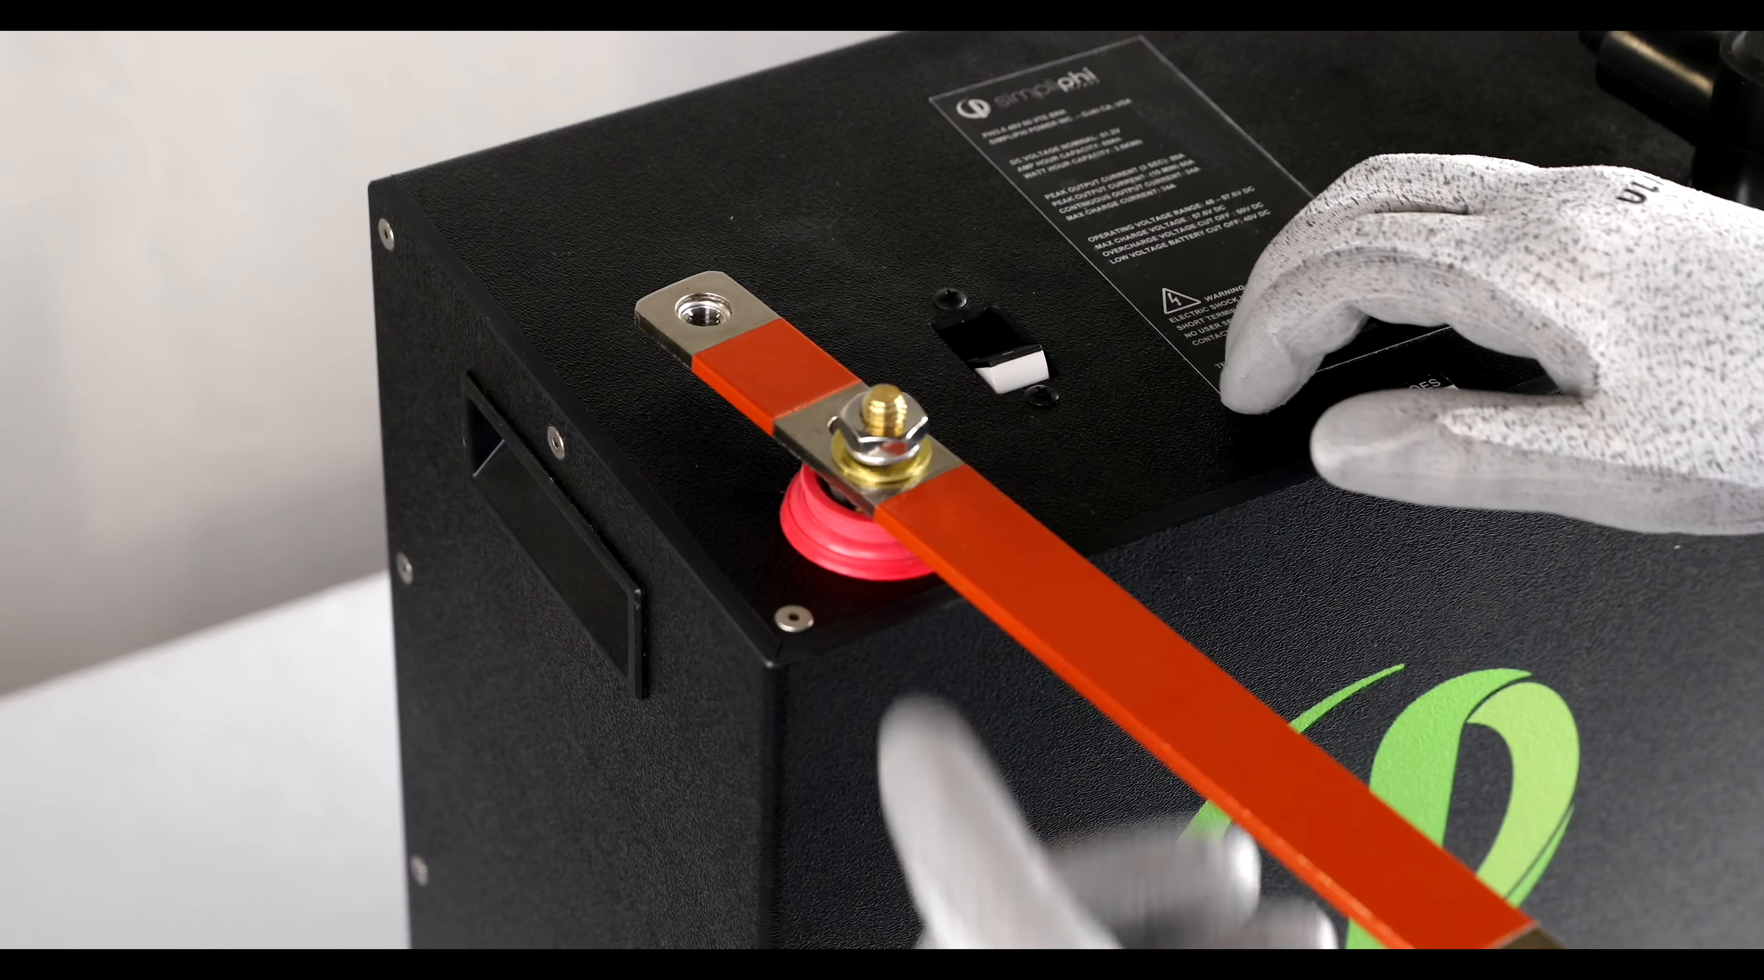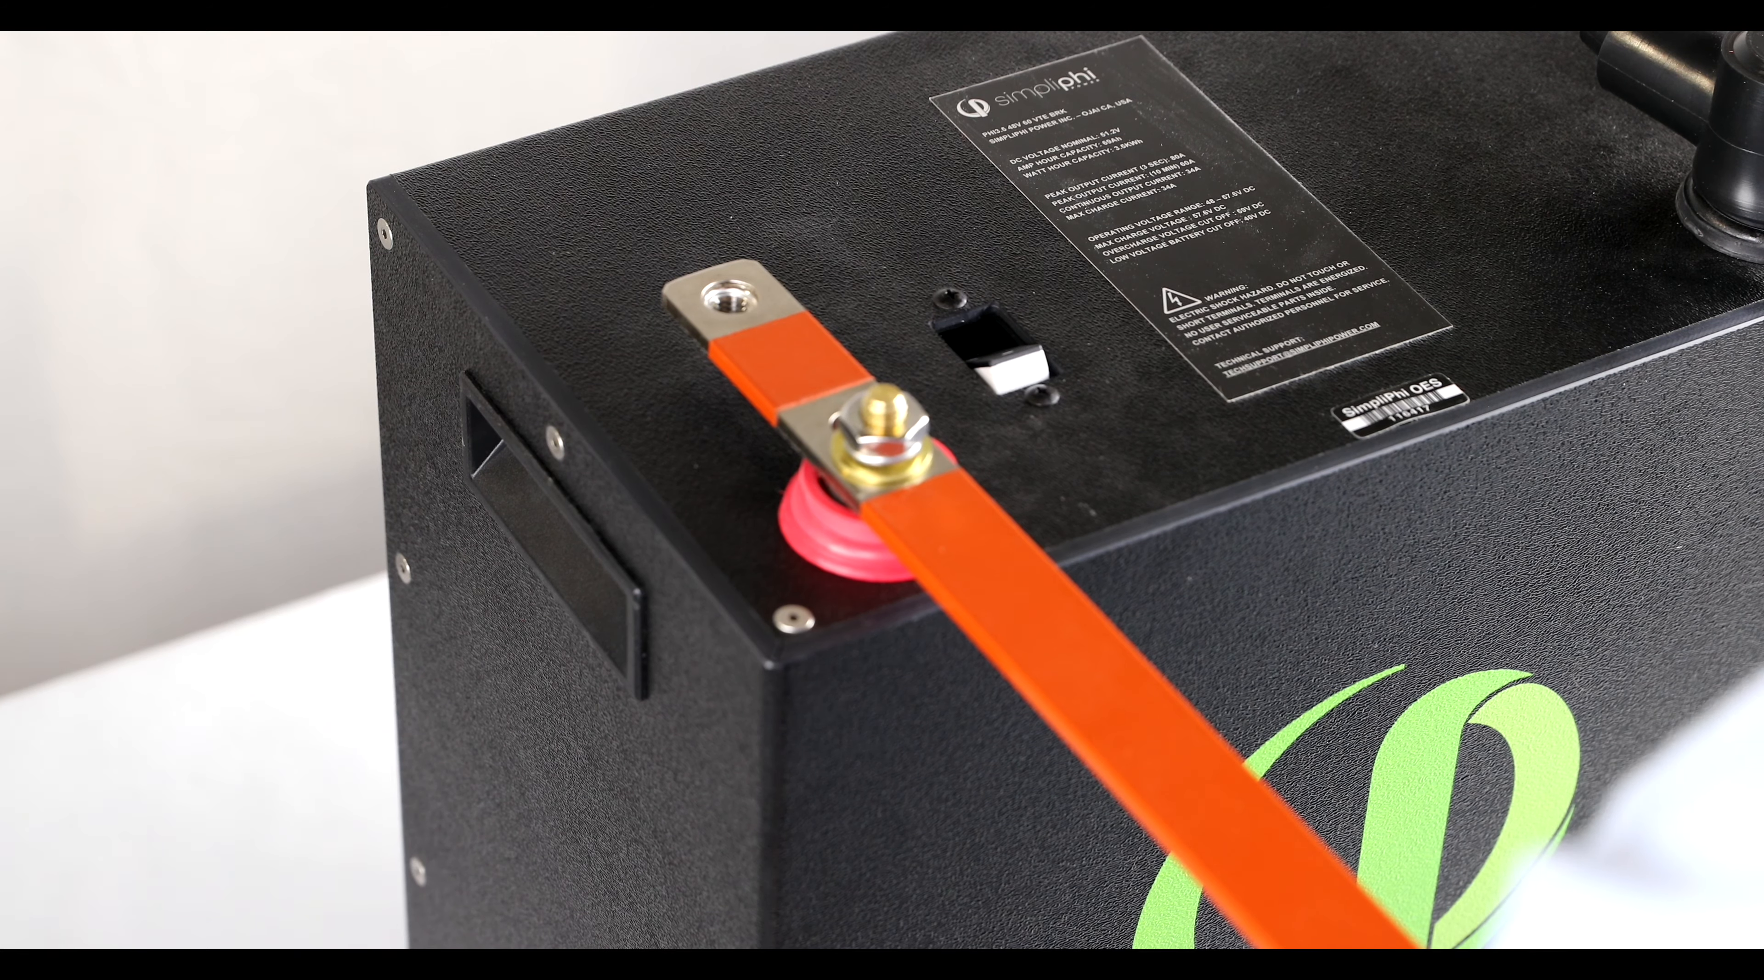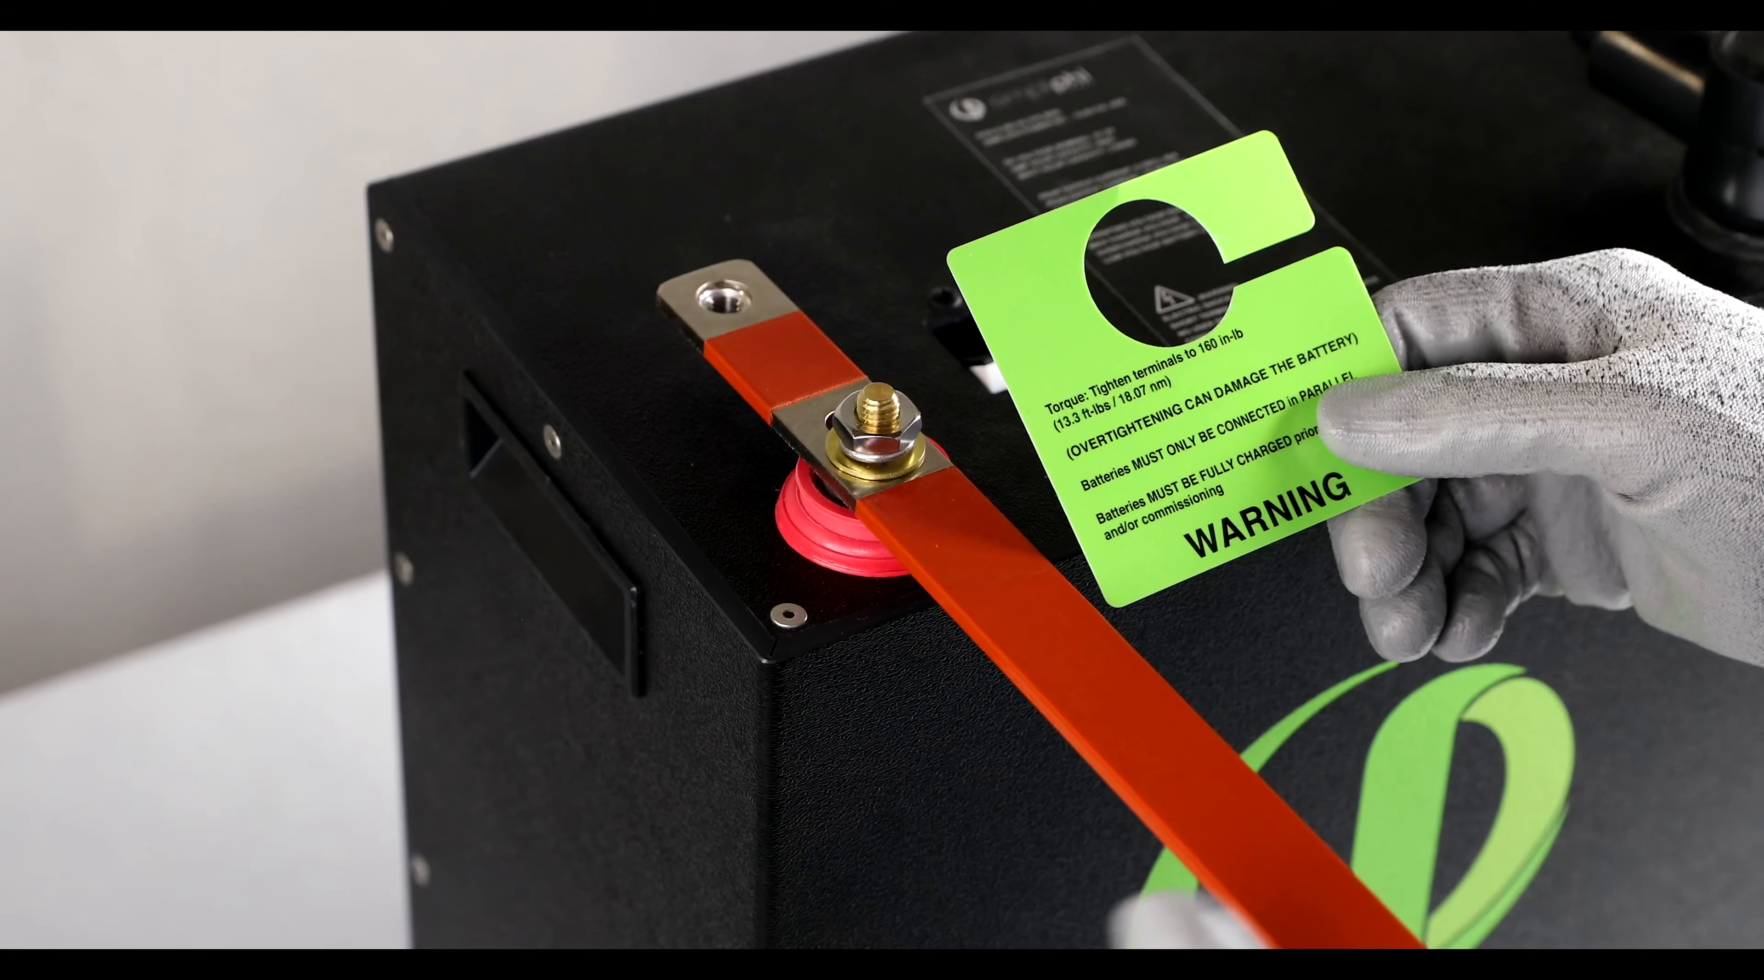Before turning the battery on, be sure to tighten the 11/16 inch stainless steel nut to 160 inch pounds.